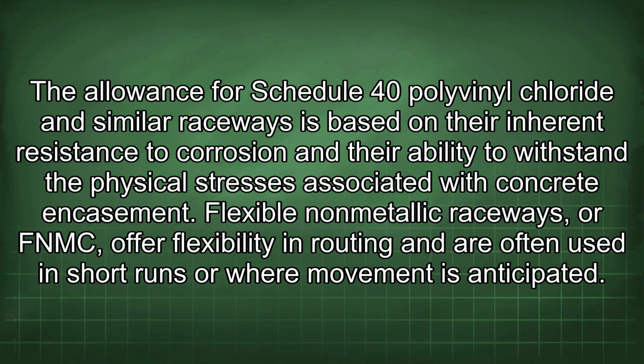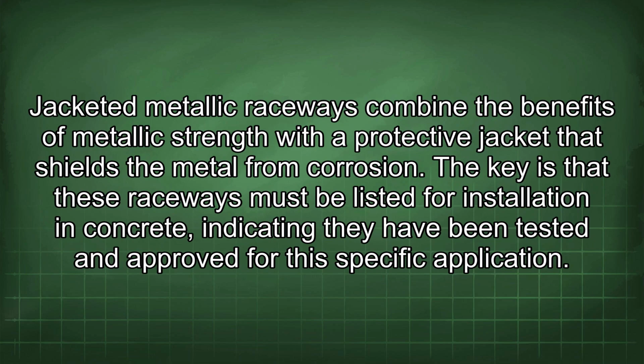The allowance for Schedule 40 polyvinyl chloride and similar raceways is based on their inherent resistance to corrosion and their ability to withstand the physical stresses associated with concrete encasement. Flexible non-metallic raceways, or FNMC, offer flexibility in routing and are often used in short runs or where movement is anticipated. Jacketed metallic raceways combine the benefits of metallic strength with a protective jacket that shields the metal from corrosion.